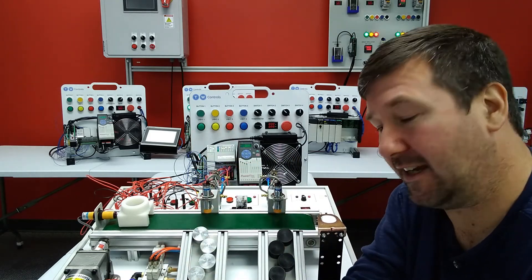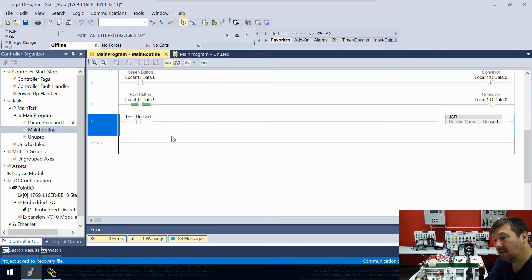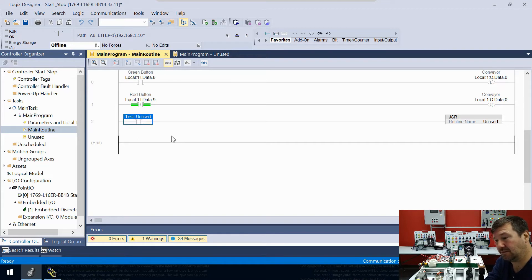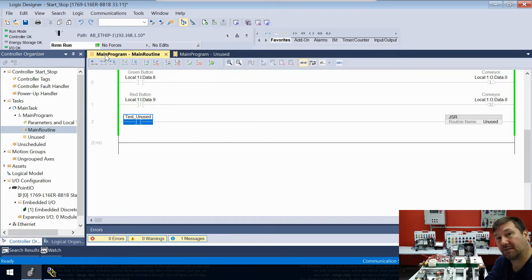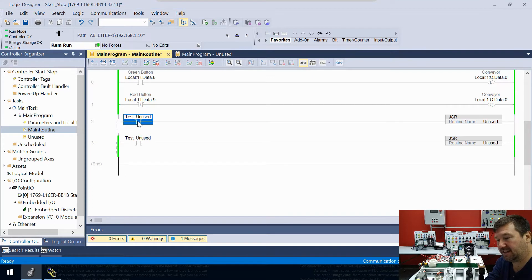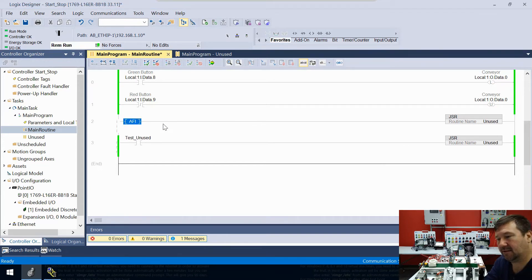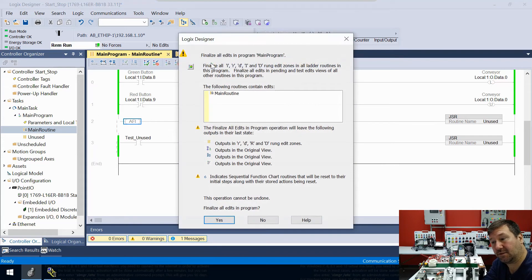A lot of people tell me that if you use an AFI it completely disables a rung — well it doesn't completely disable it, it simply makes it always false. Logic-wise it'll always be false but it's not disabled. So if we change our instruction on our test unused, let's double-click and type AFI and send that to the PLC.